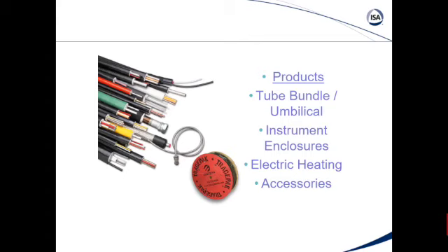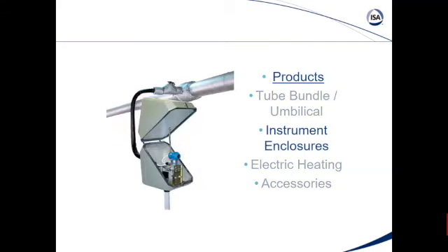and things get missed. Now, with the tube bundle product, albeit that the product is more expensive, you have one guy basically running your tube, your heat trace, your insulation, and your jacketing all in one shot. Now they may be a couple different trades terminating it: your mechanical for the tubing, the electrical for the electrical heat trace if it's traced that way. But at the end of it, you save in labor, and then at the very end, you have a much more bulletproof product in that it's that extruded jacket, really tight cable to the tube, and everything's really nice and neat. I'm 100% more confident with tube bundle than I am with conventional ways of freeze protecting tubing. And that tubing, as an example here, will terminate into a heated enclosure for a transmitter like you see here.